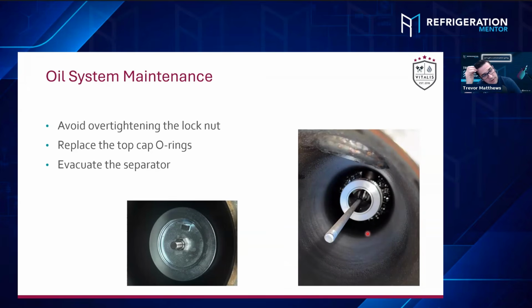And I know I've done trainings where guys are like, Trevor, well, I just put CO2 in there and blow off. You don't want to do that to purge it, because moisture or something can get in there. Yeah. You need to pull an evacuation on this every time. It takes time to do it right, because that is going to cause havoc on your system if you get moisture in there, and acid kills compressors, kills components. So definitely evacuate it.